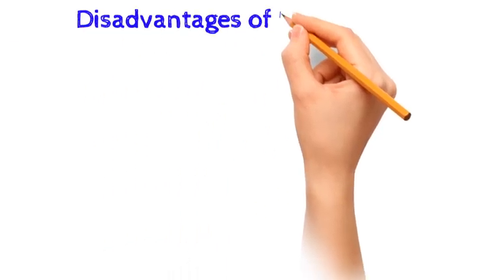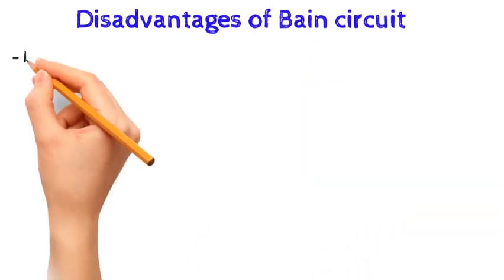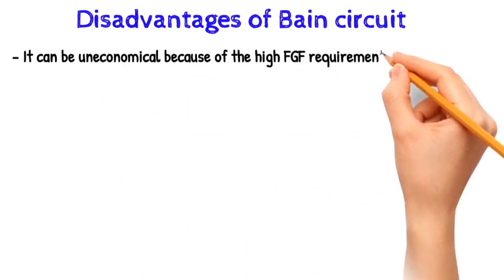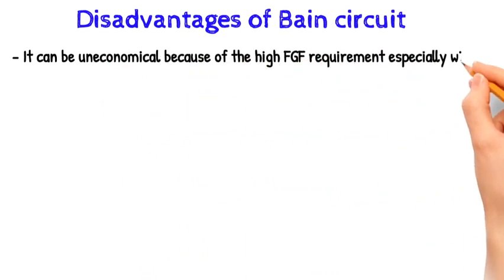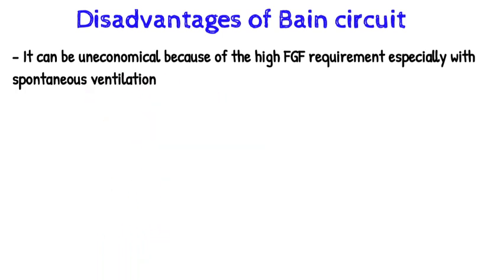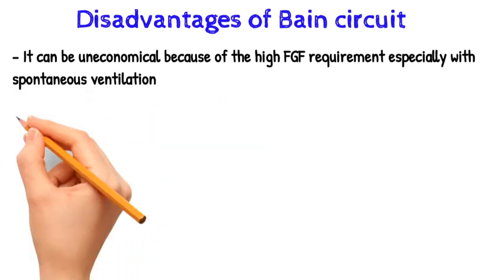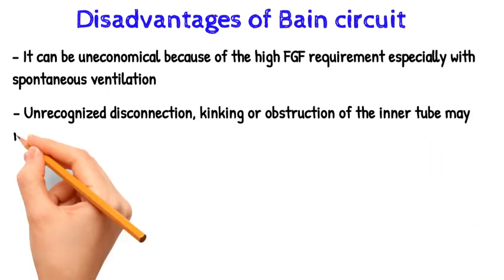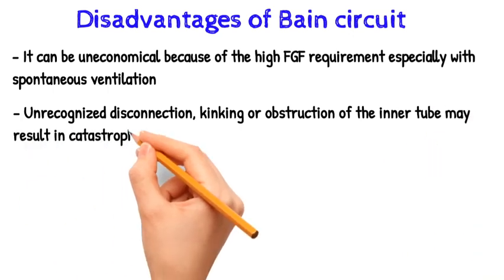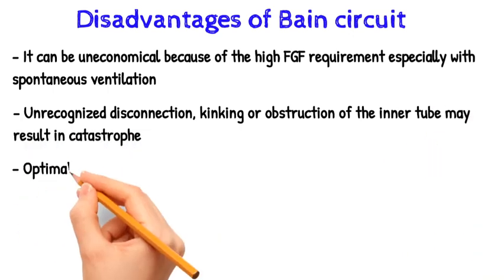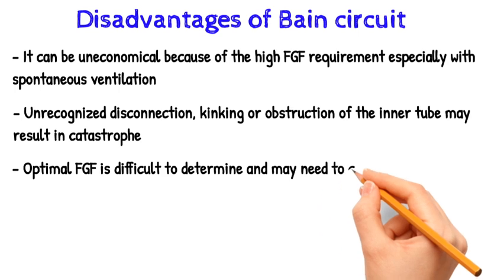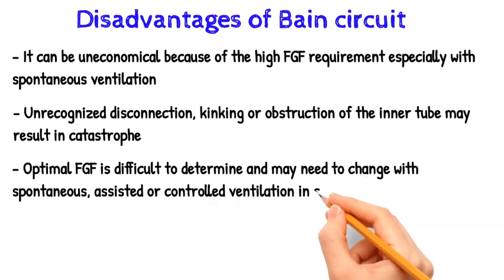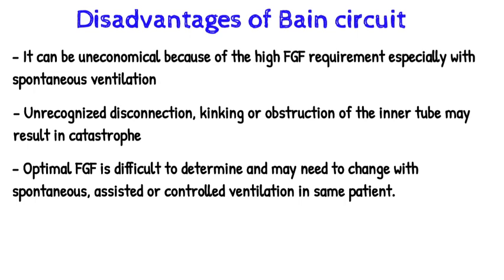Disadvantages of the Bain circuit: it can be uneconomical because of the high fresh gas flow requirement, especially with spontaneous ventilation. Unrecognized disconnection, kinking, or obstruction of the inner tube may result in catastrophe. Optimal fresh gas flow is difficult to determine and may need to change with spontaneous, assisted, or controlled ventilation in the same patient.